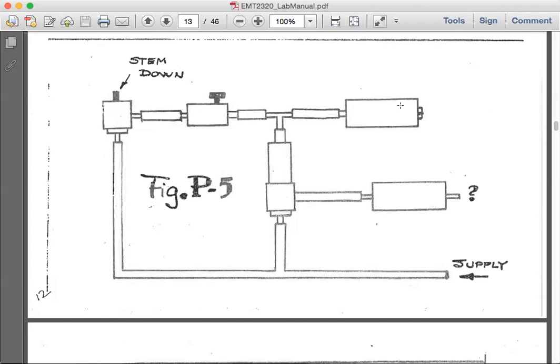Okay, so the air tank, what does it do? It basically increases the volume of the pressure in this part of the system, not in the entire system, only in this part of the system. So by increasing the volume, it takes more time to pressurize or to depressurize this part of the given system. The air tank is usually most efficient when it's used in series with the flow control.